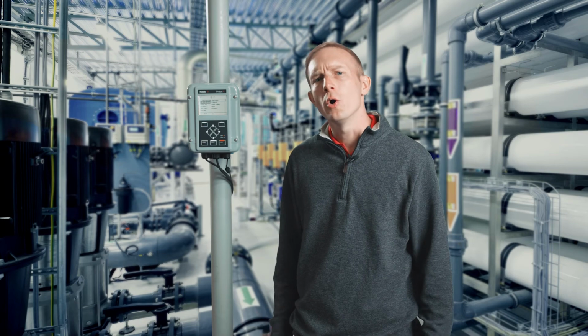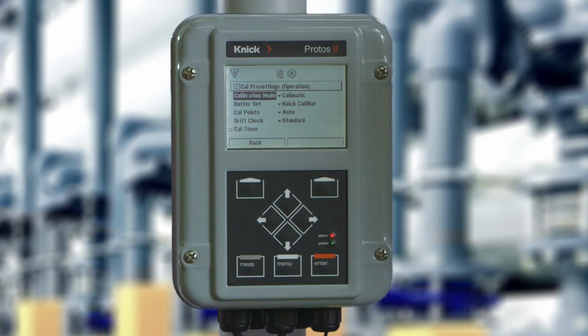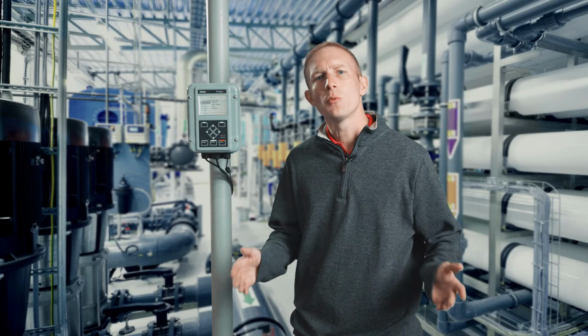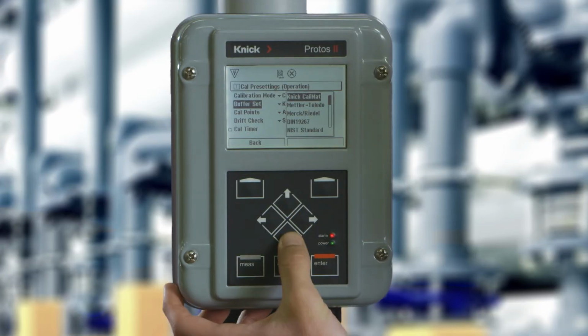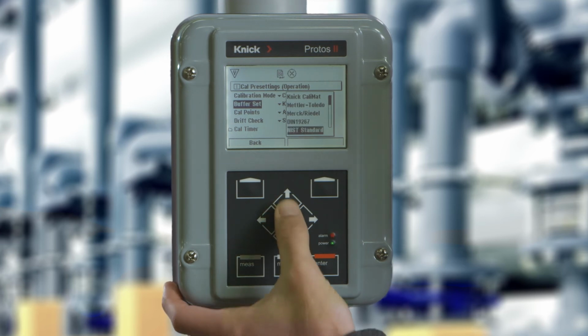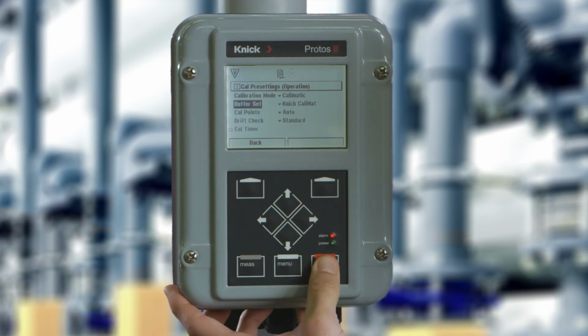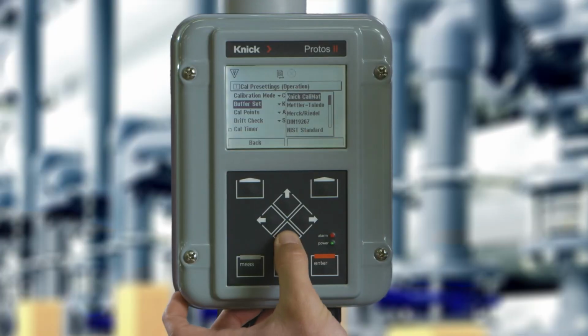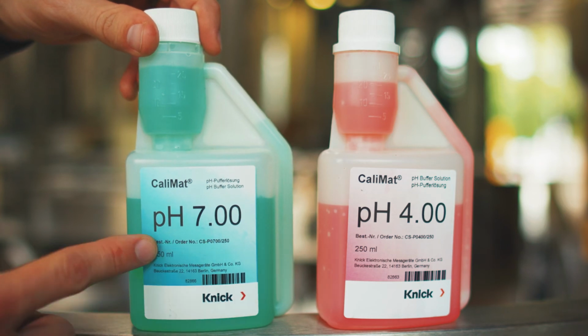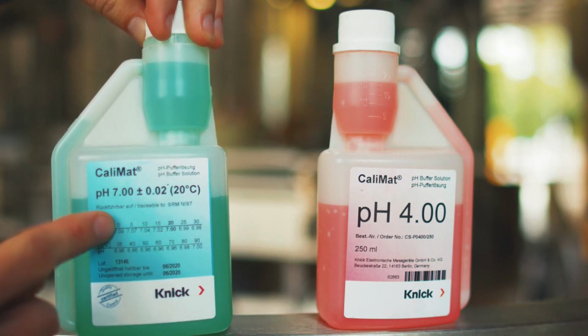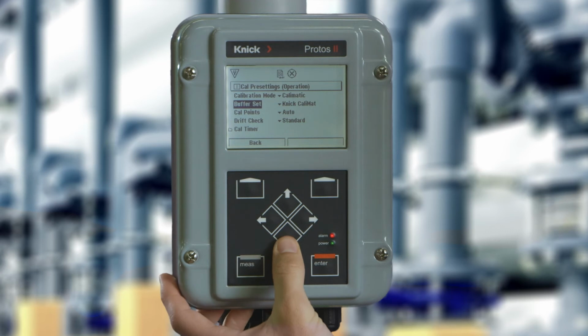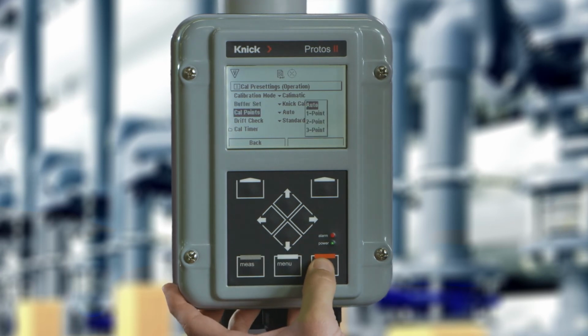We recommend Auto or Calimatic calibration, which provides automatic buffer recognition and temperature compensation. You'll see that once you've selected Calimatic under calibration mode, it then allows you to select which buffer set you are using. The most common buffer on the market is NIST Standard. You can verify your buffer set by checking the labeling on your bottles. Next, we have the ability to select the default number of calibration points, followed by the drift check of the sensor.